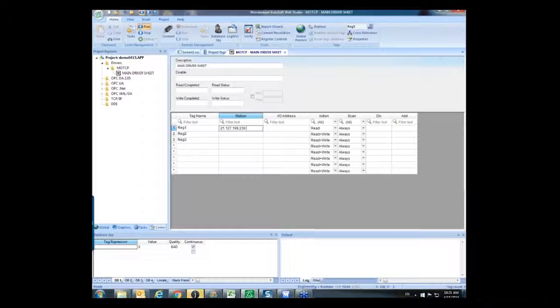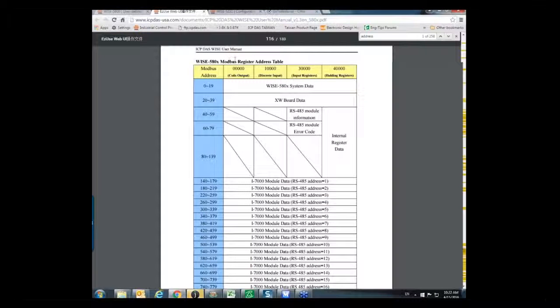So now I created a new project. I can insert a new screen here, and I put a screen 2 here. And then on tag, you need to create a project tag. Let's say I want to pull data from register 1, register 2 and register 3 from the module. After that, you need to go to COM and add a driver. I already added a Modbus TCP driver. After you add the driver, you should be able to see the main driver sheet here. Let's put in the tag.